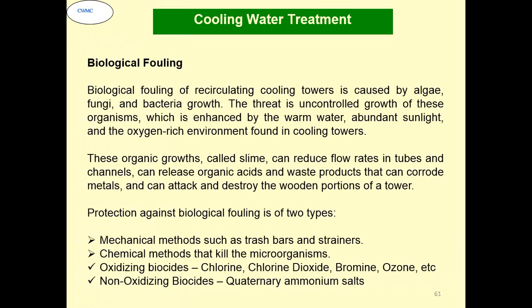Biological fouling, this is of course becoming one of the major problems these days. It's a challenge these days. Recirculating water is affected by algae, fungi and bacteria growth. The threat is uncontrolled growth of these organisms, which is enhanced by the warm water, abundant sunlight and the oxygen-rich environment found in cooling towers. These organic growths, called slime, can reduce flow rates in tubes and channels, can produce organic acids and waste products that can corrode metals, and can attack and destroy the wooden portions of a tower.